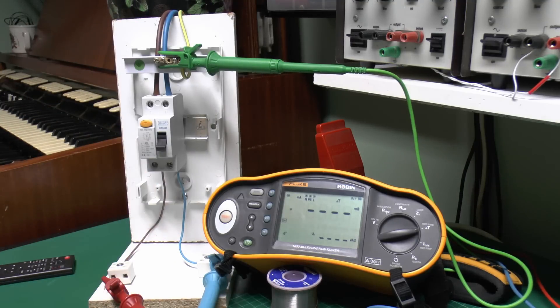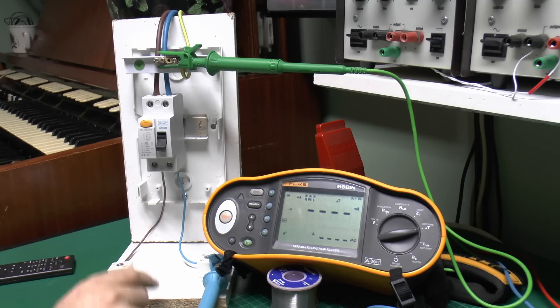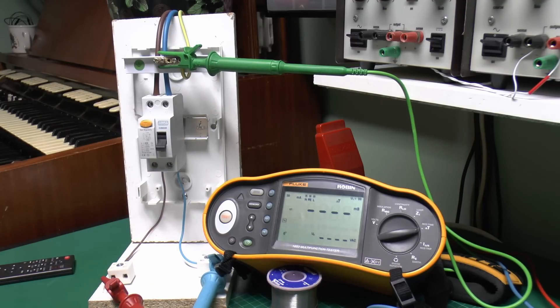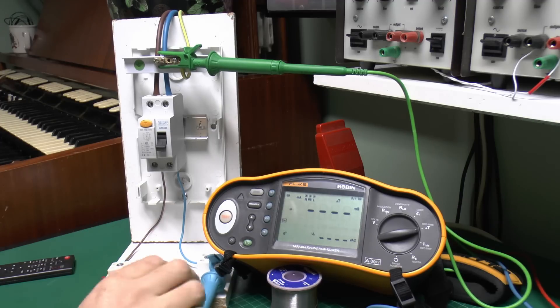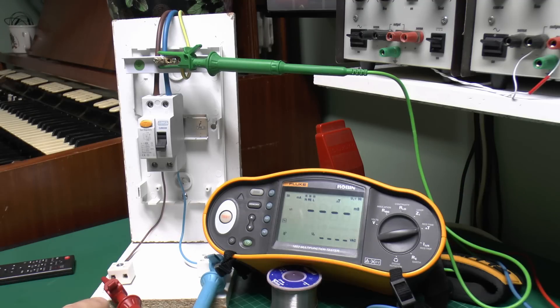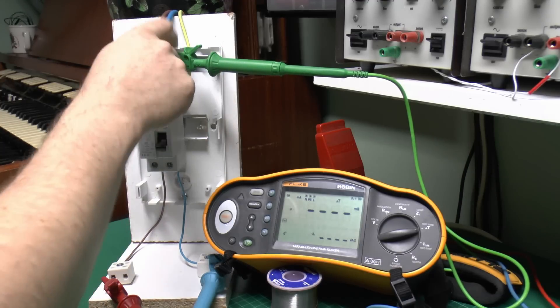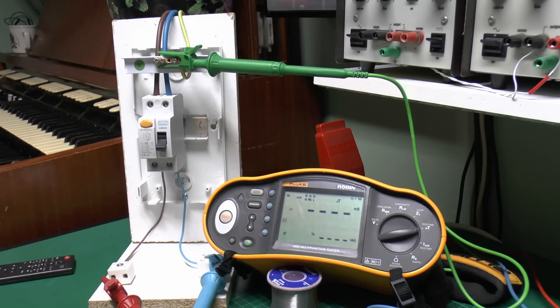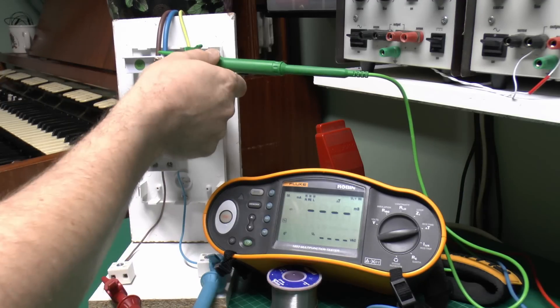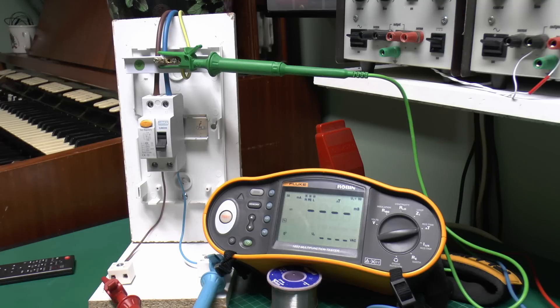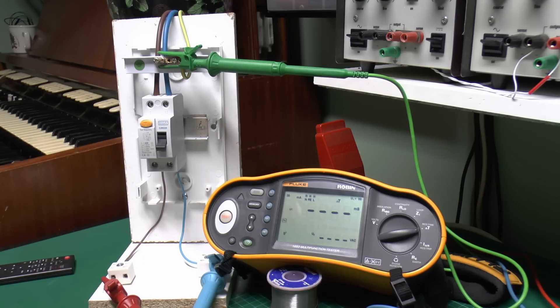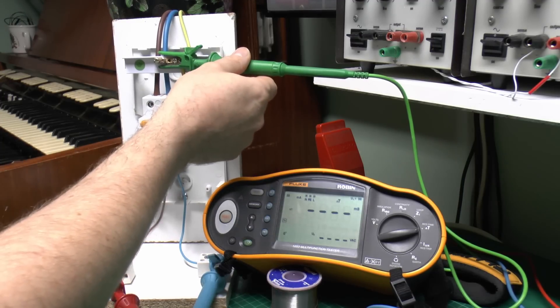Now in theory, you could test an RCD just by having a current imbalance between the line here and the earth over here, and you wouldn't actually need the neutral. But testers generally have the three leads connected for several reasons, one of which is to make sure you've actually connected these to the correct polarity. Obviously, if you connect this to the neutral, then the tester won't actually work. And the other reason is so that before the test is actually done, it does a check to make sure that you're not going to have any dangerous voltages appearing on the earth to the rest of the installation. Clearly, if that was not connected properly somewhere, just actually doing the test and putting a current between here and here could actually create a fairly high voltage on the earth or other metalwork within the installation, certainly something which you need to avoid. So that's basically why these testers have the three leads. Although of course when the test is done, it's simply putting a current between the line here and of course to earth there, so then you've got the imbalance at the device you're testing.